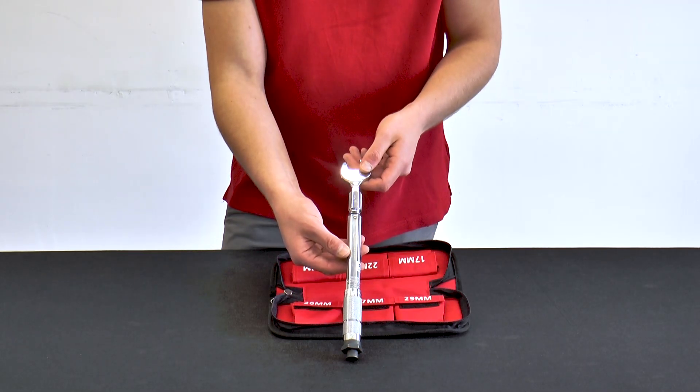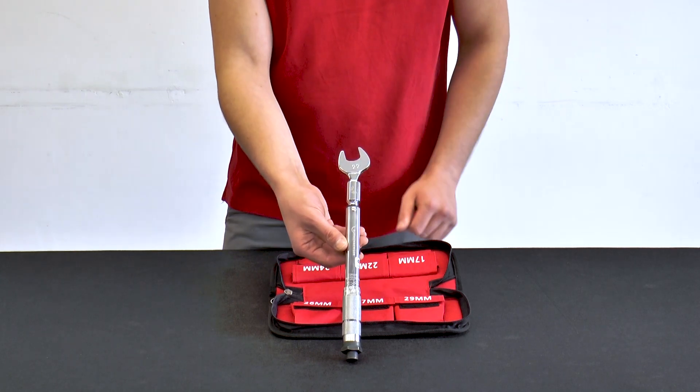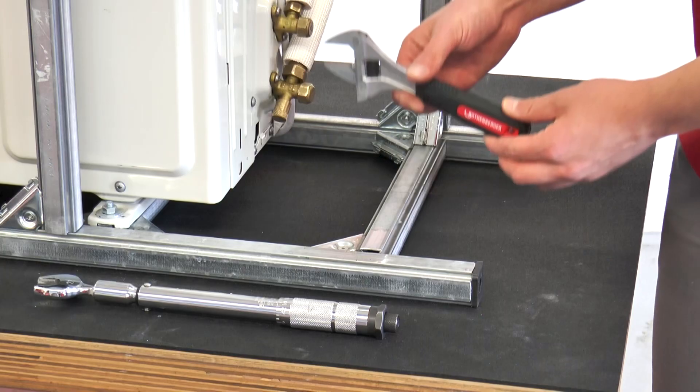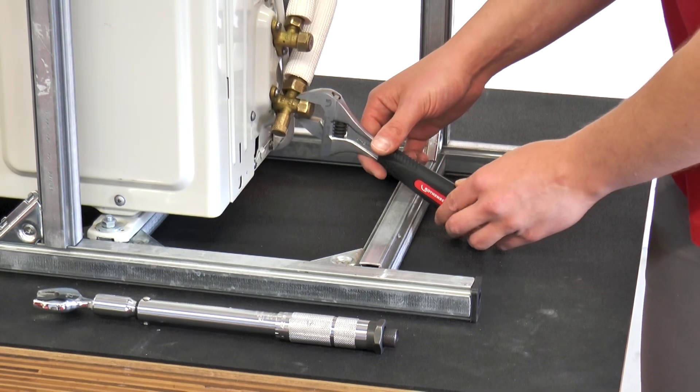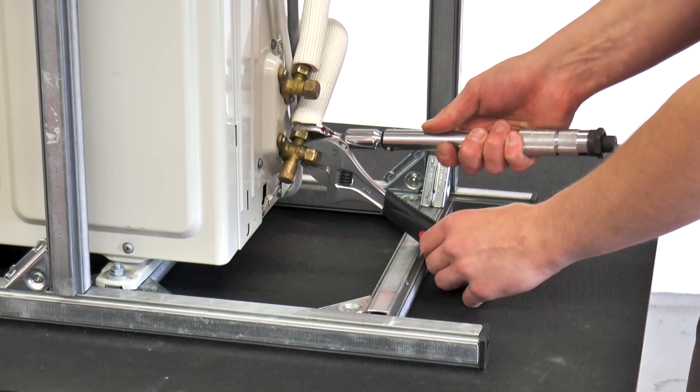After the torque wrench has been set to the required tightening torque, the flare nut can be tightened with the torque spanner. A roller fork wrench is used for counter holding. The flare nut is tightened until the torque wrench makes a loud cracking sound.